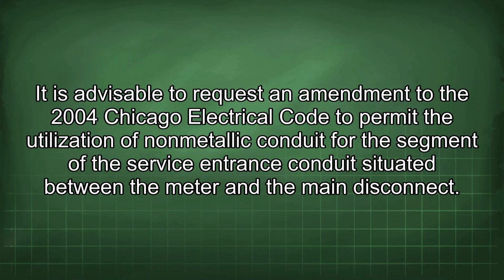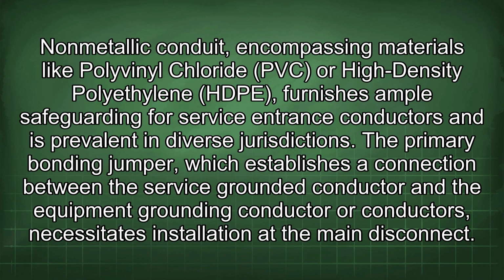It is advisable to request an amendment to the 2004 Chicago Electrical Code to permit the utilization of nonmetallic conduit for the segment of the service entrance conduit situated between the meter and the main disconnect. Nonmetallic conduit, encompassing materials like polyvinyl chloride (PVC) or high-density polyethylene (HDPE), furnishes ample safeguarding for service entrance conductors and is prevalent in diverse jurisdictions.